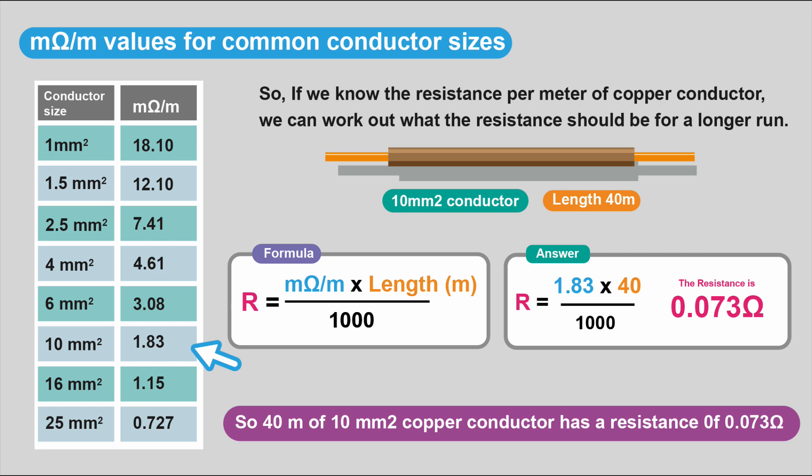And here we have another example. This time it's 10 millimeter squared conductor. Let's have a look. 10 millimeter squared conductor has a value of 1.83 milli-ohms per meter. So we do the same sum.